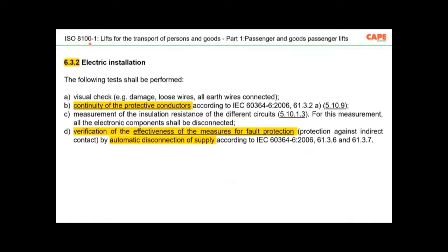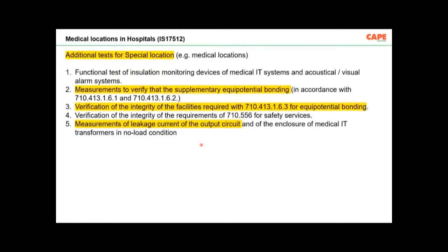8100, the lift, the new upcoming standard, which is going to become an Indian standard. You see here, first is the visual check. Next one is continuity of the protective conductor. Means the wire, the resistance of the wire, it must be very, very small. Number D, verification of the effectiveness of measures of fault protection against indirect contact by automatic disconnection of supply. So the standards are actually very well documented and very well written in these subjects. But unfortunately, we don't do exactly what is recommended. Similarly, in a hospital, additional test for special location. What is a special location in a hospital?